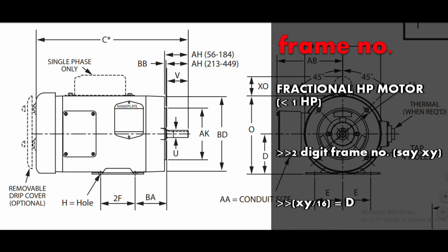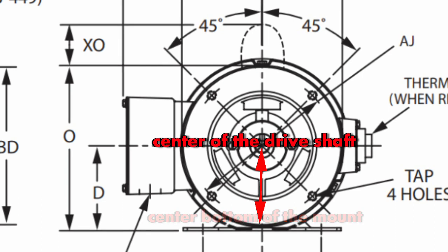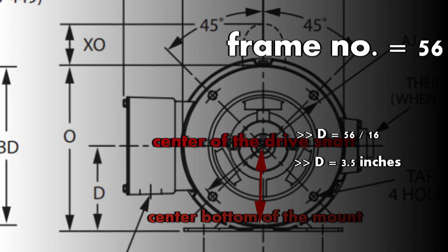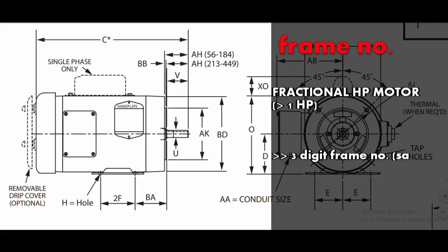Next comes the frame number. If your motor is rated less than one horsepower — that is called a fractional horsepower motor — the frame number will be two digits. By dividing those two digits by 16 you can find dimension D, which is the distance from the center of the drive shaft to the center bottom of the mount in inches. For example, frame number 56 divided by 16 gives three and a half inches.